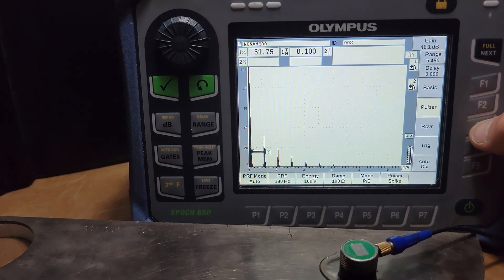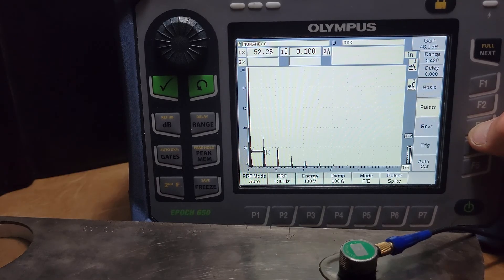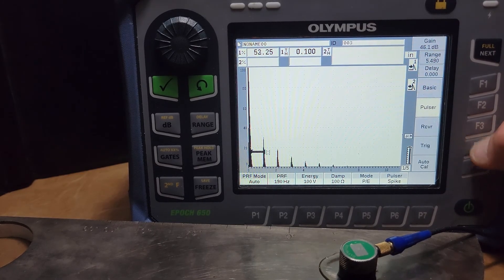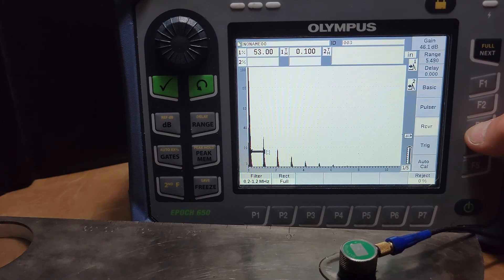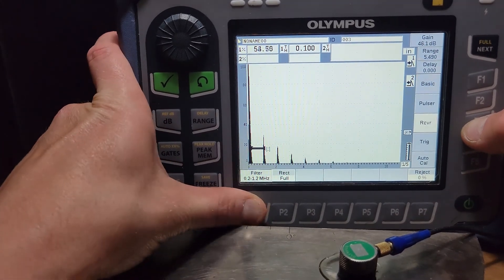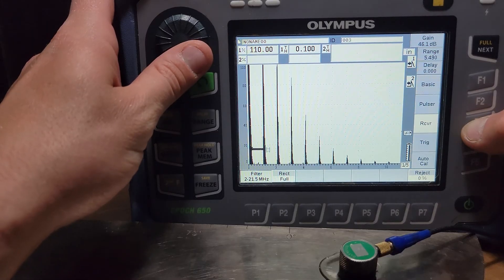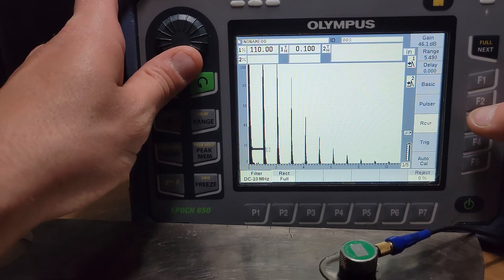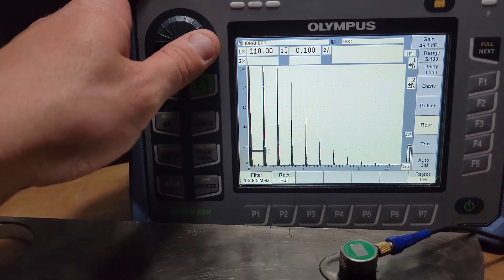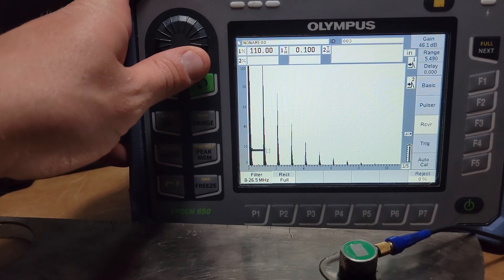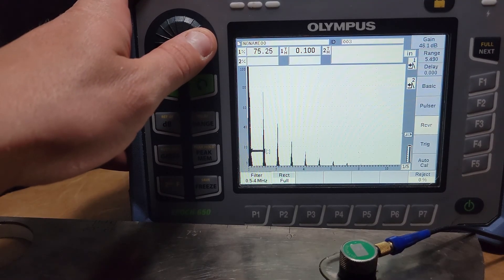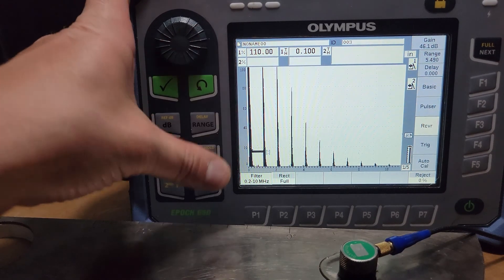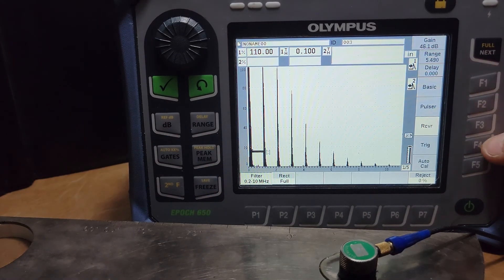Next under there is pulser where we can change some of the voltages and dampings, pulse rep frequency, into the receiver where we're changing filters which would change the receiver. Essentially if you've got an amplifier nearby you can put on a filter to where it blocks out high pass, low pass, kind of that business there. You want that to encompass your sound, so I kind of like point two to ten here looking the best.